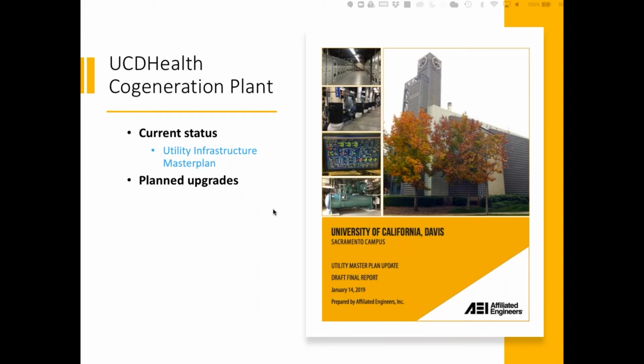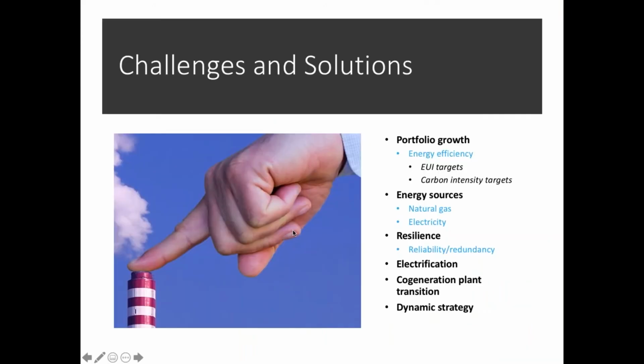So we need to address that in concurrence with looking at how we're going to adjust the plant in the future. Part of that involves things like heat recovery chillers, which operate at a much lower hot water temperature than our current distribution system. We currently distribute water with a 100-degree delta T. We'd be looking at a 40-degree delta T, and what that does to our distribution system is huge. So those are some of the things we have to be looking at as we go forward.